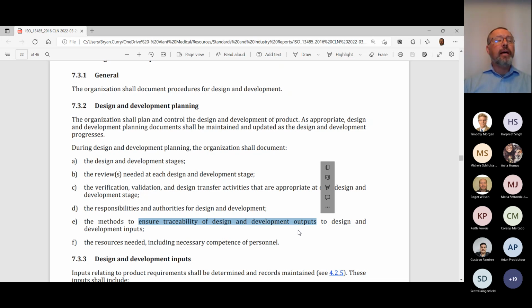If you've ever heard of a design inputs requirements document, sometimes referred to as a DIRD, sometimes referred to as a user requirements document, essentially it's a matrix. It looks very much like a control plan or almost like an FMEA, where you have all of the design inputs listed down the y-axis, and then as you go across the x-axis, you connect each input to an output, and then either the method of verification or validation. Whether it's going to be part of your control plan, or a validation strategy where you reference the validation report, you have to be able to connect the dots for each one of those things.